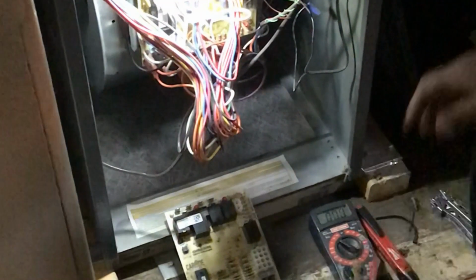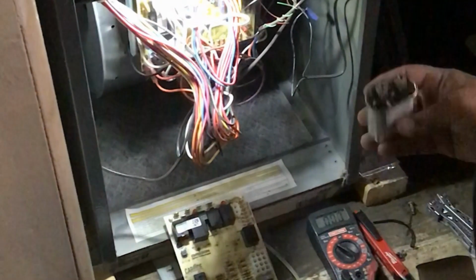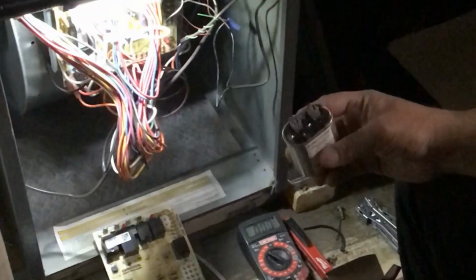Just like we talked about earlier, another component is your indoor blower motor, which also has a capacitor, just like the outdoor fan, except it's not a dual capacitor. It just supplies the fan. We'll show you one out of the case in a second. Okay, so we were talking about a capacitor. Just like the outdoor unit, the indoor fan is going to have one as well. It's a lot smaller.